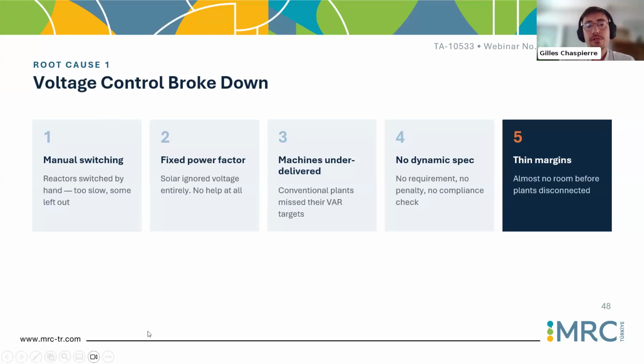Another aspect that has been observed is that a lot of synchronous machines, unfortunately, did not deliver as expected. When an asset connects to the system, it needs to be compliant with your national technical rules. And I don't know if it was not properly checked or if something was not well behaving at the moment, but the situation is that big machines that we would have expected to absorb a lot of megavars were really, really below the target. So it's important, of course, when a new asset connects to the system, to do what is necessary to test and validate that it's compliant with the technical rules.